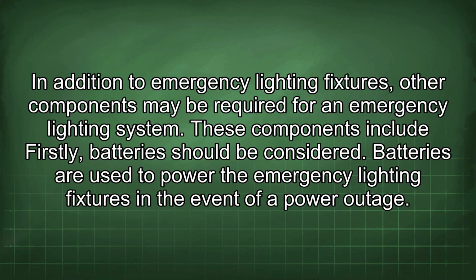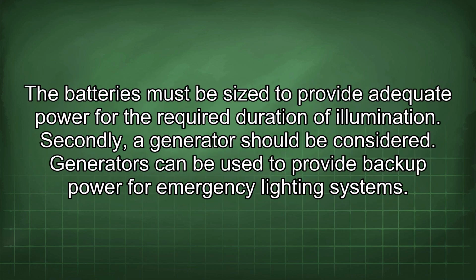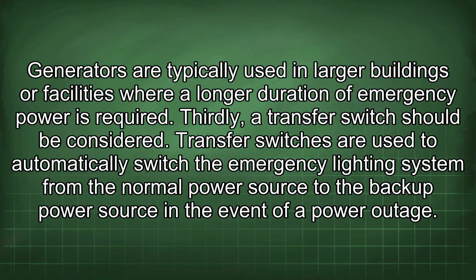In addition to emergency lighting fixtures, other components may be required for an emergency lighting system. These components include, firstly, batteries. Batteries are used to power the emergency lighting fixtures in the event of a power outage. The batteries must be sized to provide adequate power for the required duration of illumination. Secondly, a generator should be considered. Generators can be used to provide backup power for emergency lighting systems. Generators are typically used in larger buildings or facilities where a longer duration of emergency power is required.